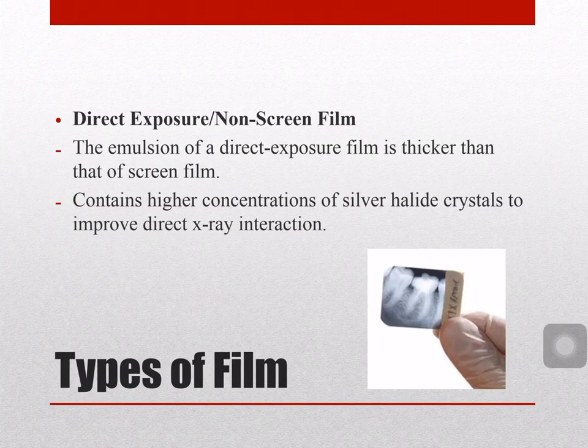There are two types of film. The first is direct exposure or non-screen film. In a direct exposure film, the emulsion is thicker than that of a screen film, and it has only a single emulsion. It contains higher concentrations of silver halide crystals to improve direct x-ray interaction. Because a direct exposure film doesn't use an intensifying screen, it cannot use a film cassette — a special type of cardboard must be used instead.